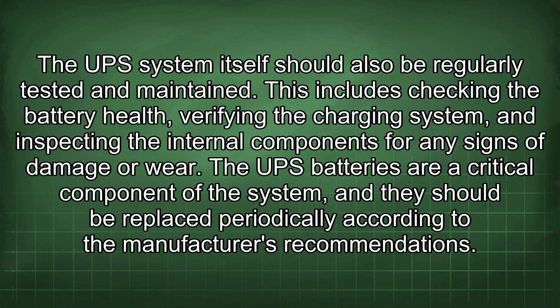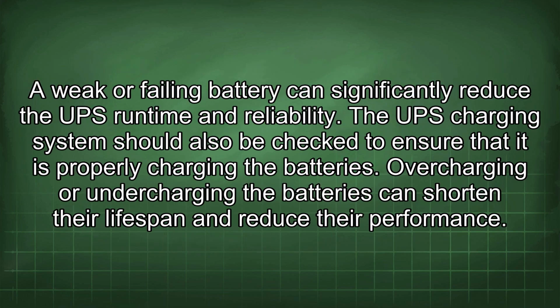This includes checking the battery health, verifying the charging system, and inspecting the internal components for any signs of damage or wear. The UPS batteries are a critical component of the system, and they should be replaced periodically according to the manufacturer's recommendations. A weak or failing battery can significantly reduce the UPS runtime and reliability. The UPS charging system should also be checked to ensure that it is properly charging the batteries. Overcharging or undercharging the batteries can shorten their lifespan and reduce their performance.